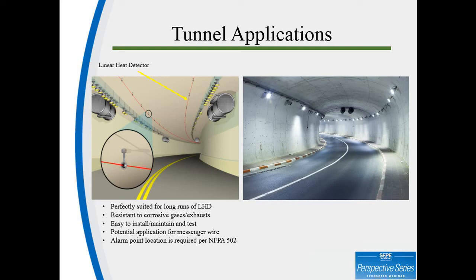There is more information about messenger wire and its applications located on our website. But lastly, I'd like to talk about NFPA 502, which requires you to identify a tunnel hotspot within 50 feet. With the resistance value calculations or alarm point location meters offered in the control equipment, linear heat detection can easily comply with NFPA 502's requirement.